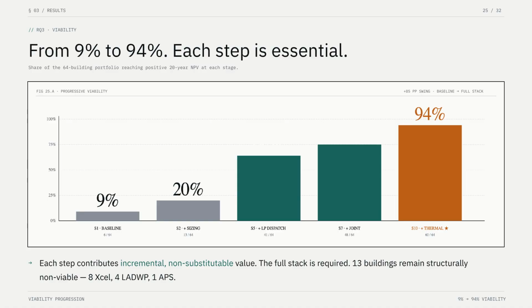Research question 3, viability. It's 9% under industry standard rules. Optimal sizing doubles it to 20. LP dispatch triples it to 64%. Joint sizing and dispatch reaches 75%. Thermal flexibility pushes all the way to 94. Each step contributes incremental, non-substitutable value. You cannot skip any of them.